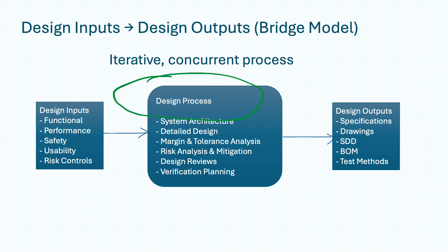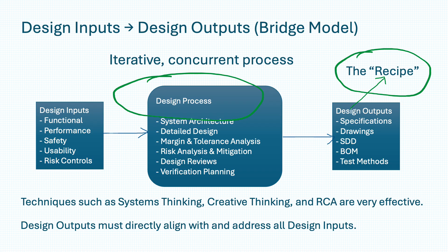Keep in mind that this process is iterative, where engineering, risk management, and usability run concurrently to ensure that the design choices address all safety, performance, and usability concerns. The tools you may use include, but are not limited to, CAD software, FMEA for risk management, coding software for software management, systems thinking and creative thinking, among others. Systems thinking, creative thinking, and root cause analysis have proven to be very effective in my experience in design and development in the ideal creation of design outputs. As we discussed, the design outputs are the recipe. These are the tangible results of the design efforts, including technical drawings, CAD models, software code, material specifications, packaging. Outputs must directly align with and address the design inputs.